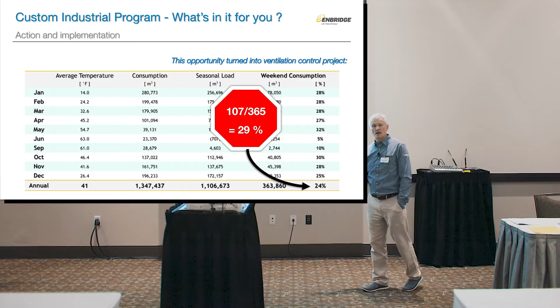Once we realized that, we got together. I brought three or four different random vendors, and he brought a couple he already worked with. We agreed and chose a vendor they used to work with on PLCs. We connected all their makeup air units, unit heaters, and exhaust fans onto a number of nodes, with a zonal controller handling inputs and outputs for all these nodes. All of that fed into the microprocessor-based facility controller, which sent information to the PC-based user interface and historian, and they also had an internet connection.